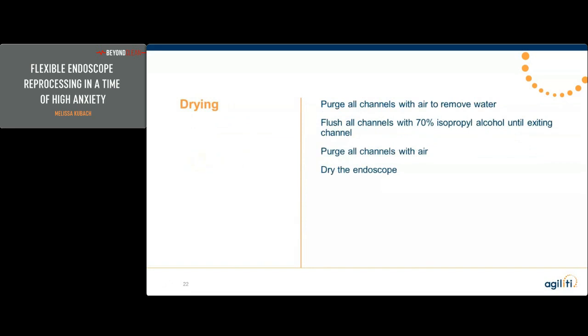Drying: purge all your channels with air to remove water. Flush all channels with 70% isopropyl alcohol until exiting the channel. Purge all the channels with air and dry the endoscope.